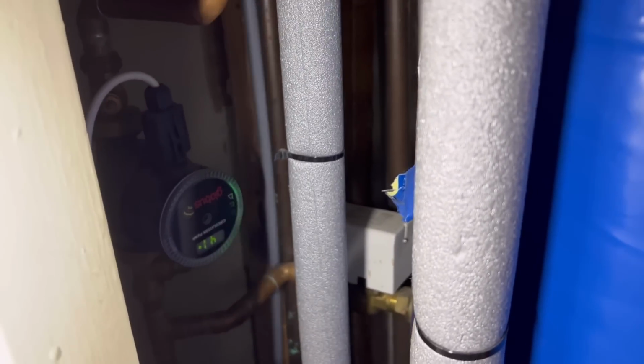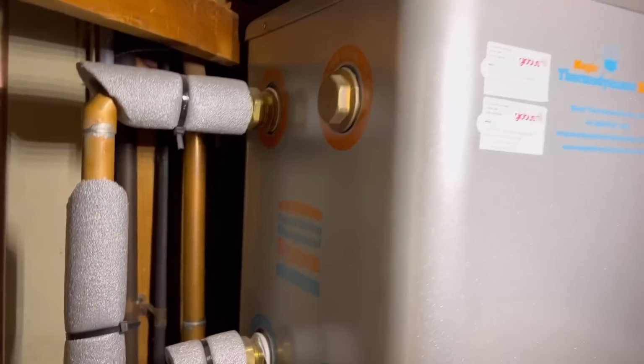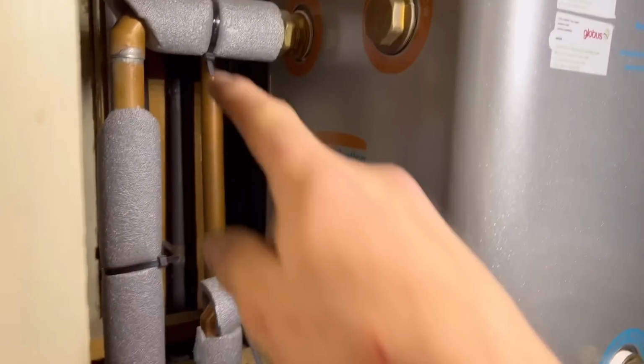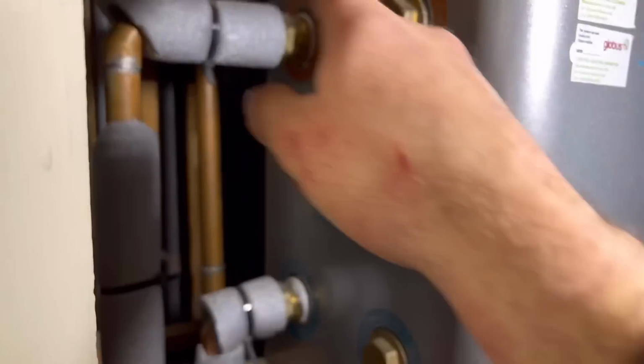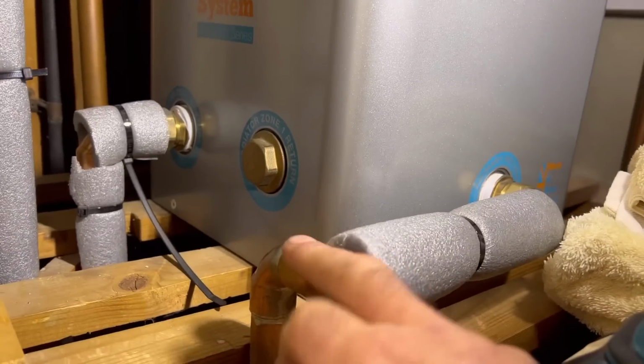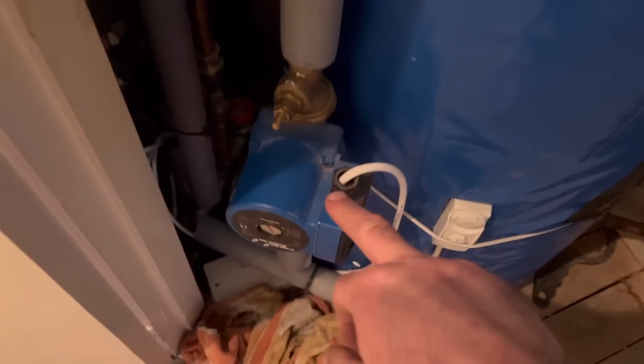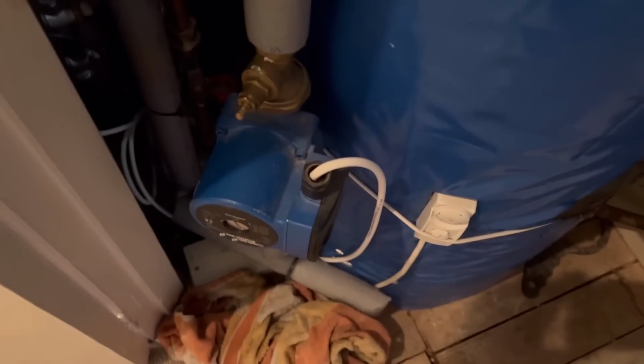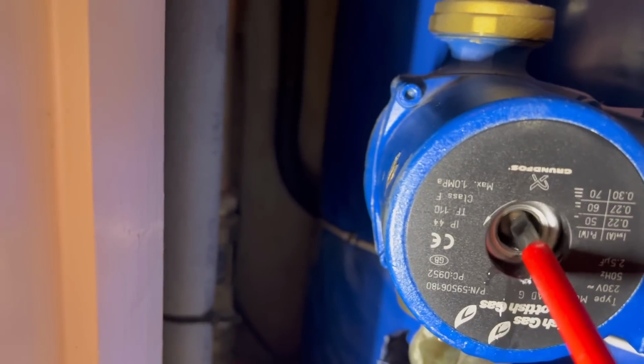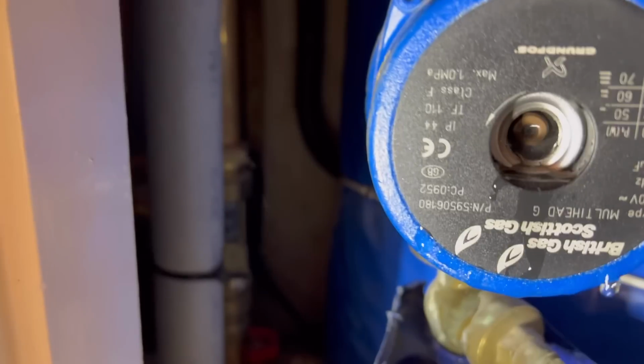Right, so I thought I'd add this in because I saw it on a job. Here you've got that little box up there, and then this little circulating pump here, which modulates up and down, so the wattage goes up and down. The flow comes up, goes into that top connection there, and circulates through and goes down, then out through that return at the bottom, at the back, and back to the boiler. Now this one at the front here is being picked up by this pump, and then it gets pushed out to the radiators.